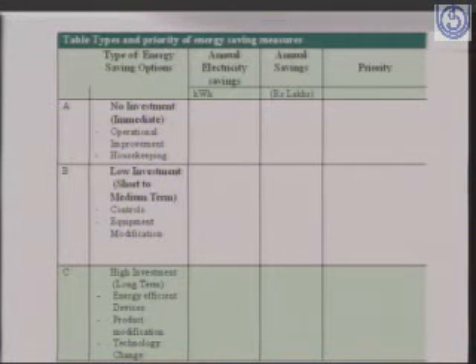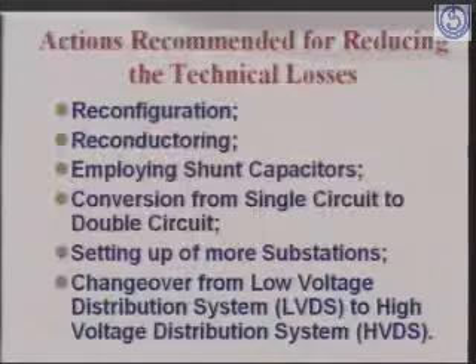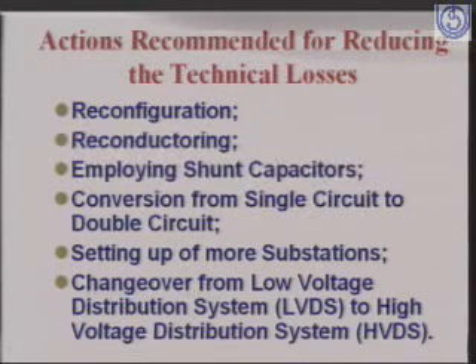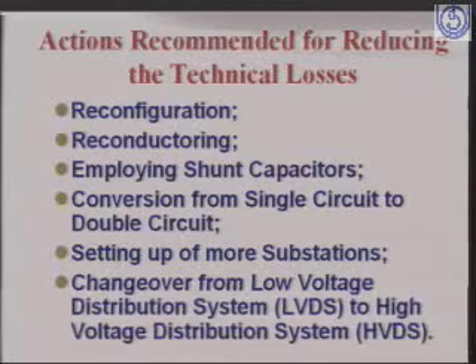So when recommendations are being made, it has to be categorized in many forms, whatever you feel like. First it has to have housekeeping or no investment measure, then low investment, then high investment. And then actions are recommended how to reduce the technical losses. It could be reconfiguration, it could be reconductoring, it could be going in for power factor capacitors, then converting single circuit to double circuit, then setting up of more substations, then changeover from low voltage distribution system to high voltage distribution system. All these measures are now being tried by majority of our utility or the distribution systems.